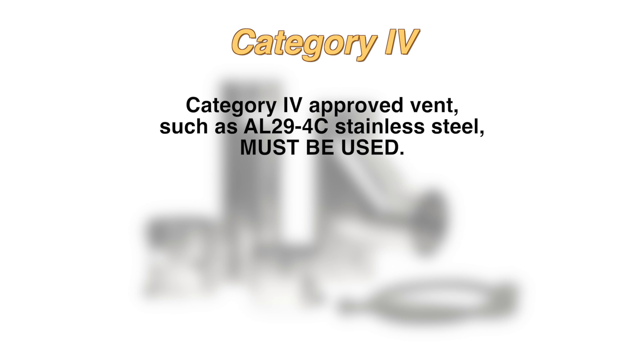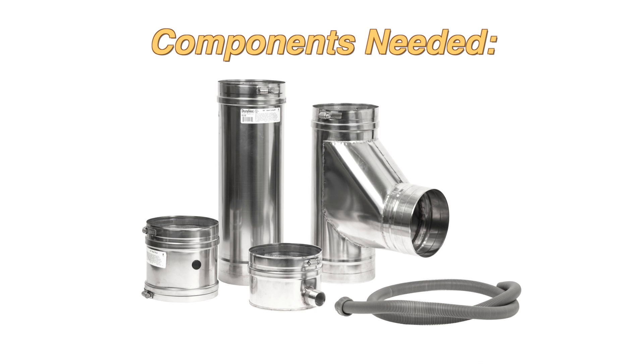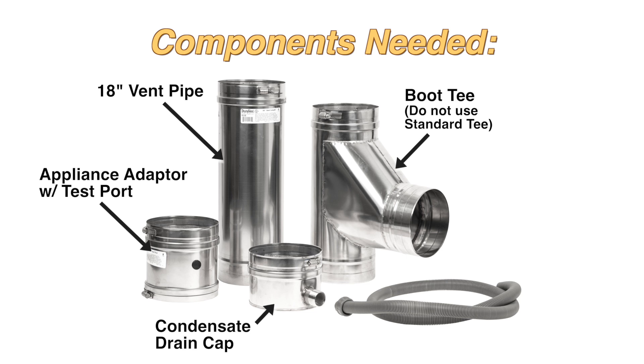Category 4 approved vent, such as AL29-4C stainless steel, must be used. We used Duravent in this demonstration. The components you will need are an appliance adapter with a test port, an 18 inch vent pipe, a boot tee, a condensate drain cap, and a condensate hose.